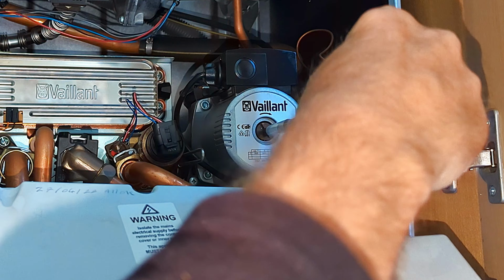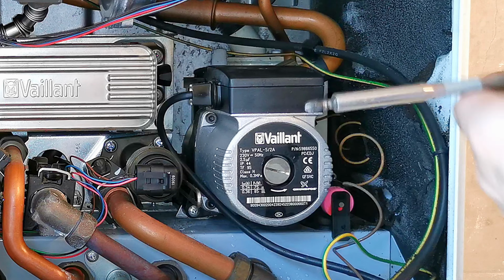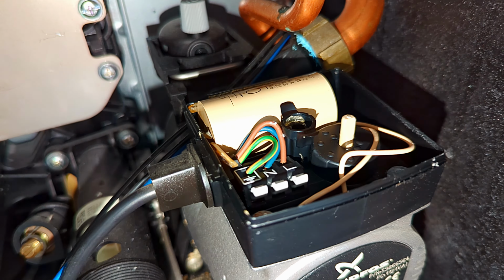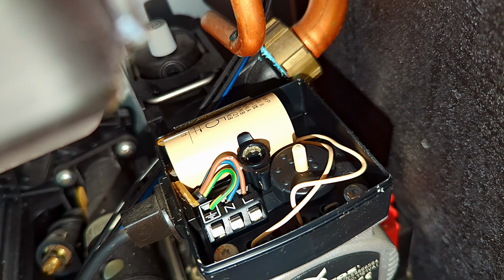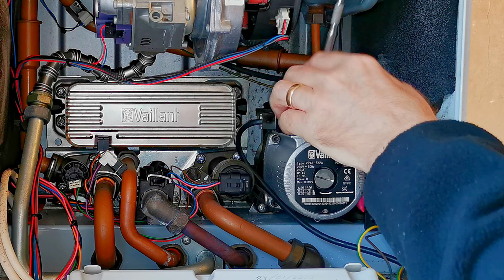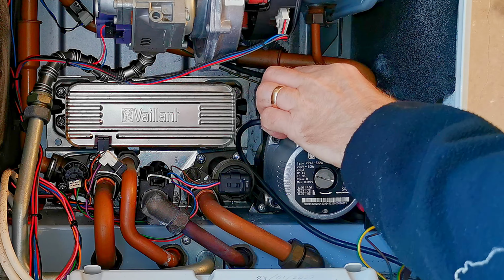Now I could always check to make sure that there is power going to the pump by removing the electrical cover on the top of the pump and checking with a multimeter, and that would prove that the pump has actually got power. If the pump's got electrical power and the shaft's not spinning, then the pump is definitely faulty.